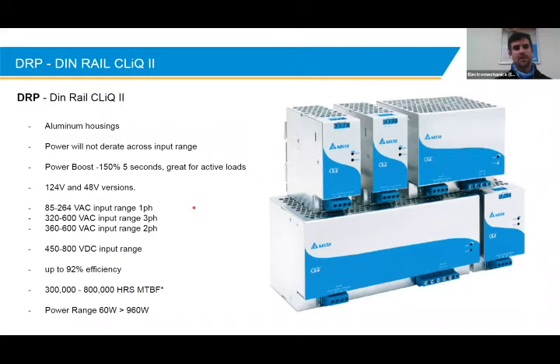Well, if you have a 100-watt power supply that's 90% efficient, that means you're basically putting 110 watts into the power supply effectively, and you're losing that 10%. So you're wasting 10 watts of energy continuously, say at full load. That's in heat. That adds to the heat in your panel. Those are things that you don't want.